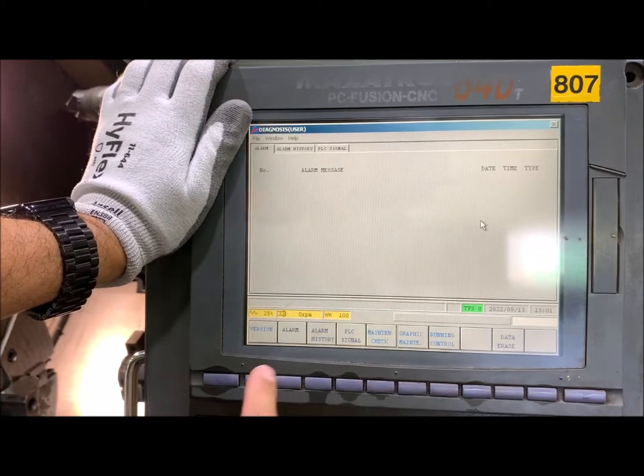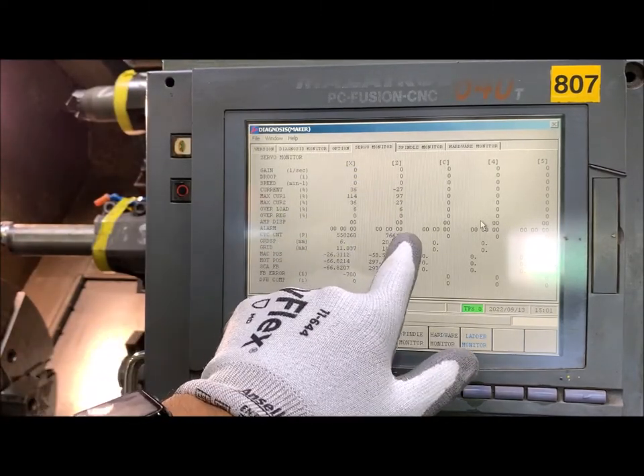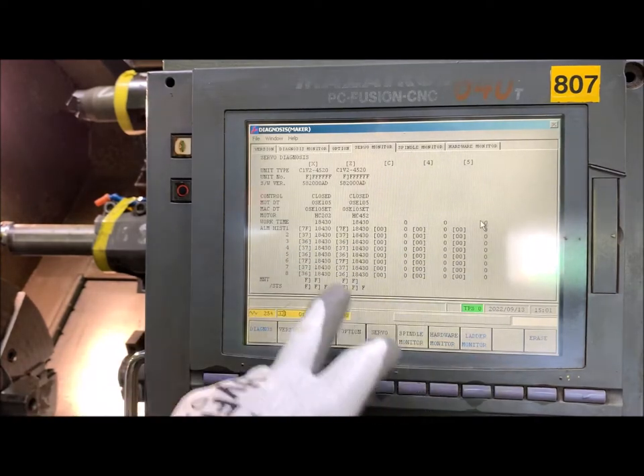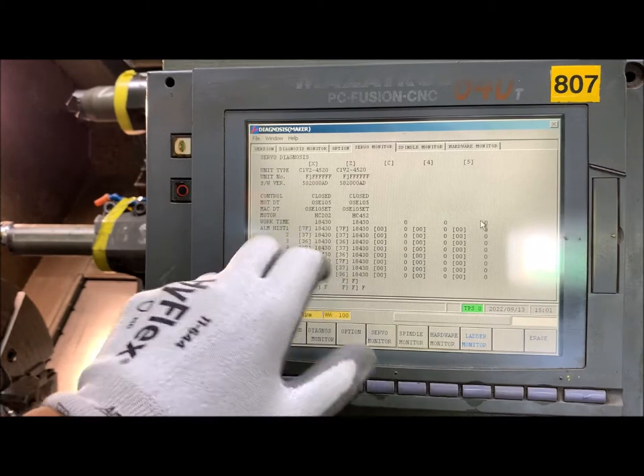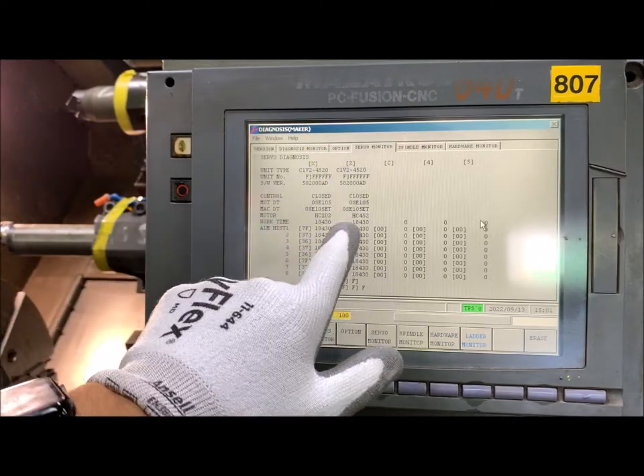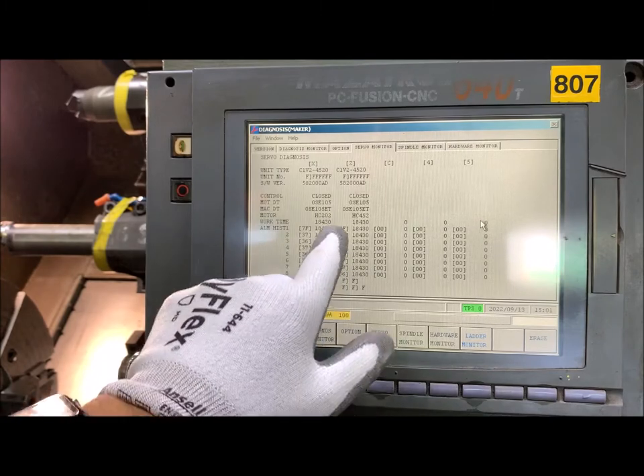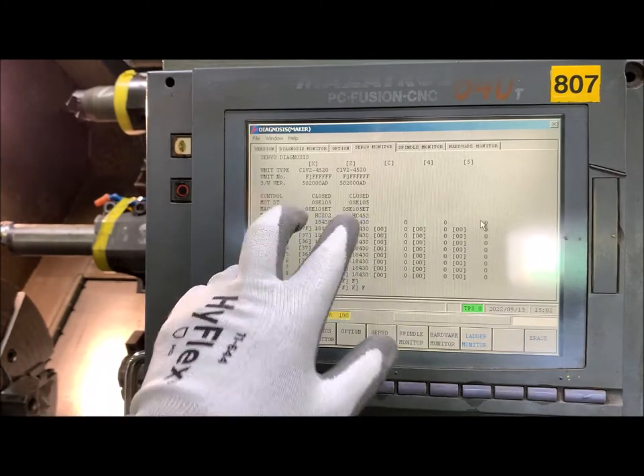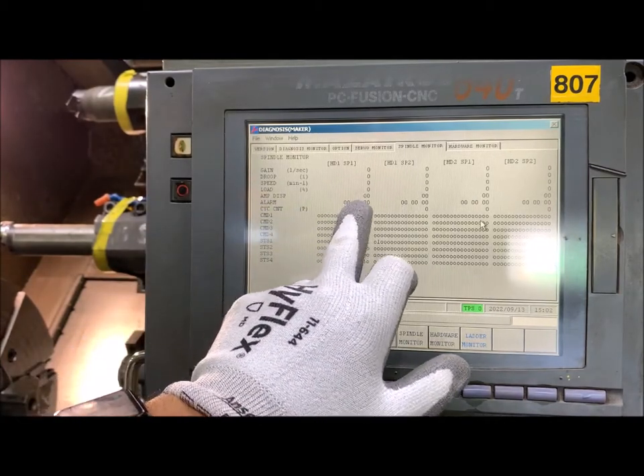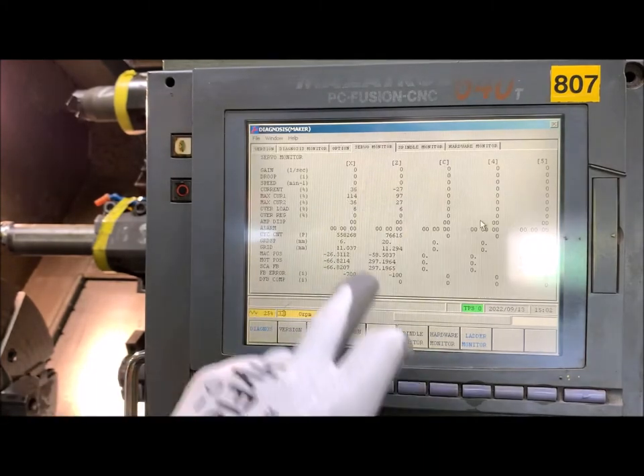If I go to diagnosis, go through version, servo monitor, I'm going to see that either the X or Z have any alarm — that's okay. Going to the next page, two pages more, I'm going to see the history. This is the last appearance in X and in Z. This is a common error after you reinitialize the CNC — the 7F. I'll leave the details for the manual in the description below. Let's go to spindle — we don't have an alarm on the drive. This is the error code you're going to see on the spindle drive or servo motor drive.